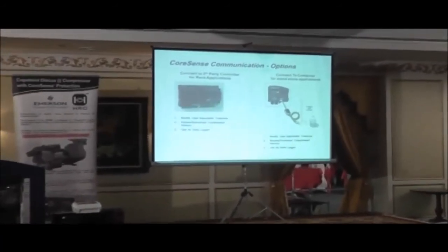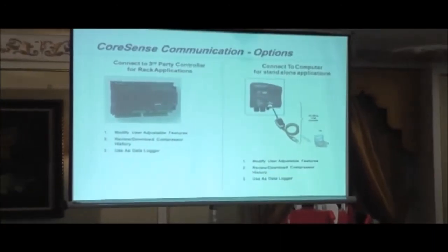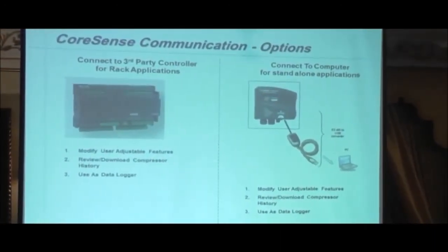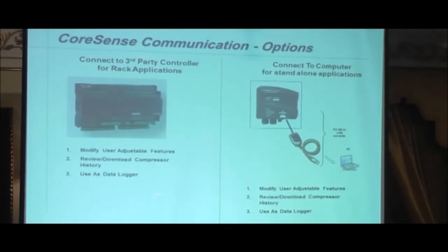This is just a representation of what I was talking about earlier on. Using a compressor as a standalone or using a compressor in a network. So here we have an example of a Dixel controller. This can be uploaded with the Modbus coding. You then can connect your compressors via daisy chain to this controller. In a standalone mode, if you wish to extract information from the compressor, you can buy software and a USB interface. Okay? You can then connect your laptop to the compressor, you can then upload all that information onto your laptop. All right, and it will help you diagnose the compressor.